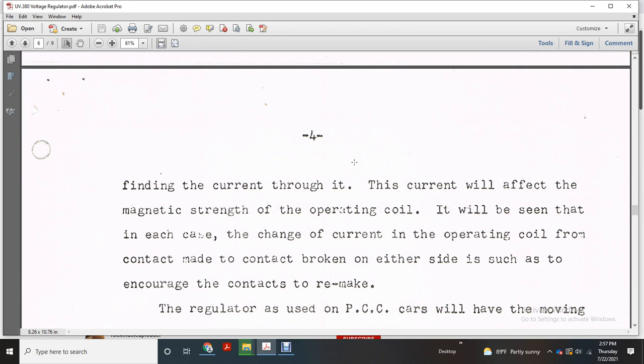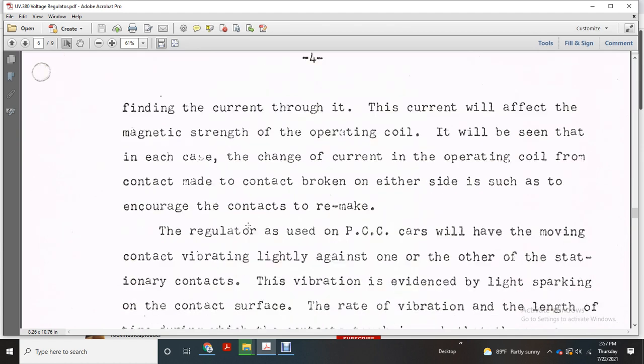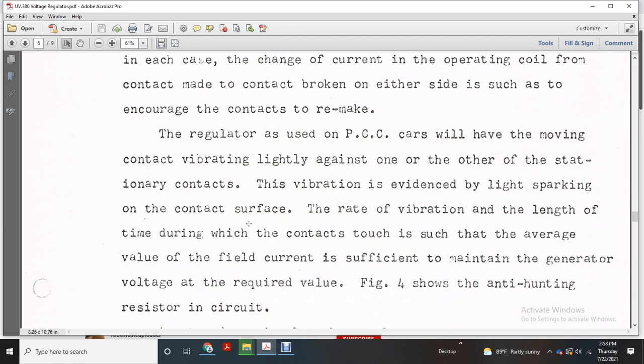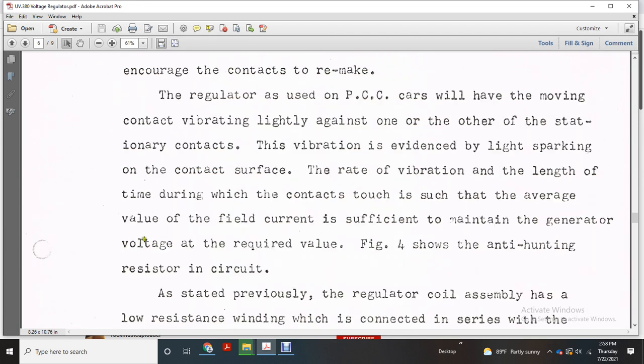The current will affect the magnetic strength of the operating coil. It will have been seen in each case that the change of the current of the operating coil, from the contact made to the contact broken, either side, will encourage the contacts to remake. The regulator used on the PCC cars will have the moving contact vibrating lightly against one or another stationary contact. The vibration is evidenced by light sparking on the contact surface. The rate of vibration and the length of time during which the contact touches is such that the average value of the field current is sufficient to maintain the generator at the required voltage value.